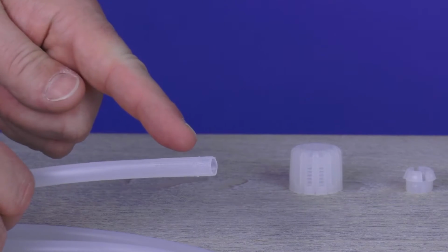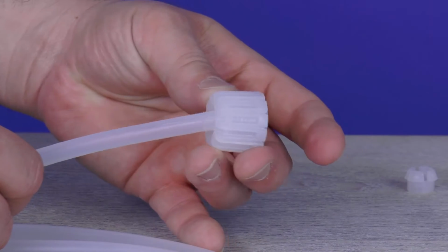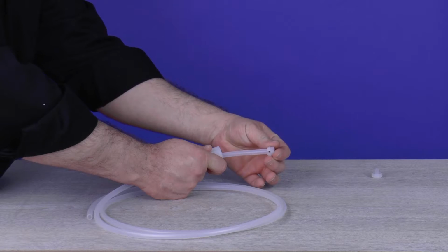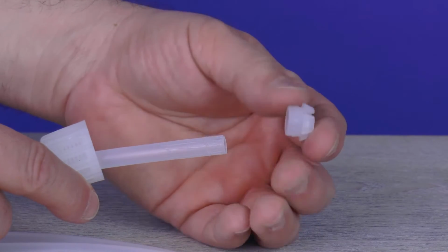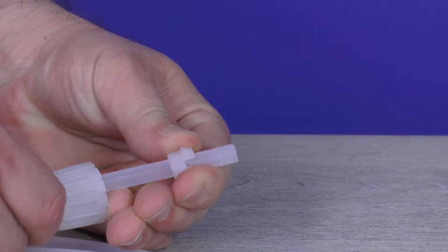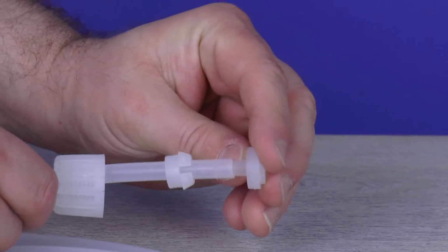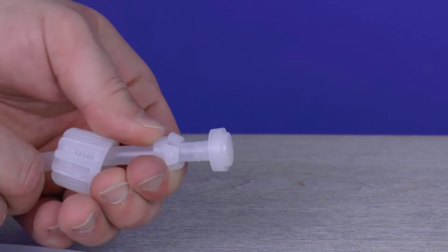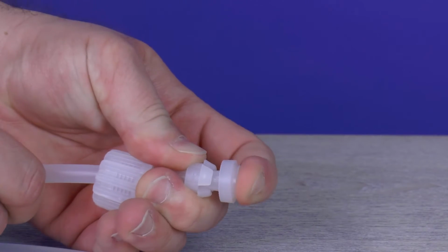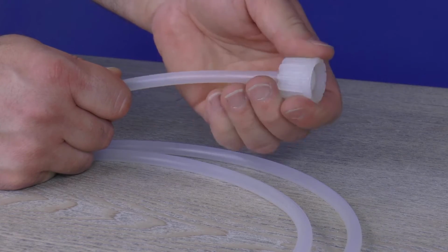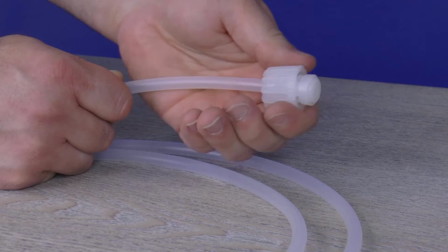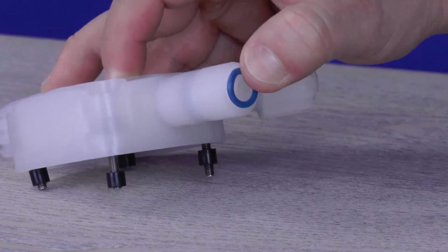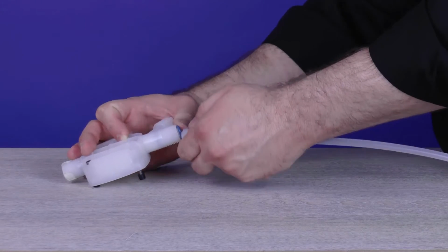Slide one end of the rigid polyethylene discharge tubing through the outside opening of the tube nut. Slide the collar onto the tube, and make sure the collar's crown is pointing away from the tube nut. Grab the nozzle and insert the pointed end into the opening of the same tube. Push the collar and nozzle together as close as possible. Pull the tube nut toward the nozzle to compress the collar and nozzle tight together, forming a ferrule connection. Place the small blue O-ring on the top of the discharge valve. Attach the tube and tube connections onto the discharge valve by hand tightening the tube nut.